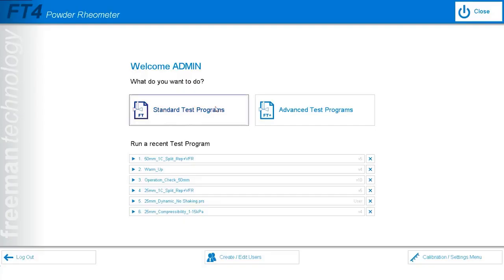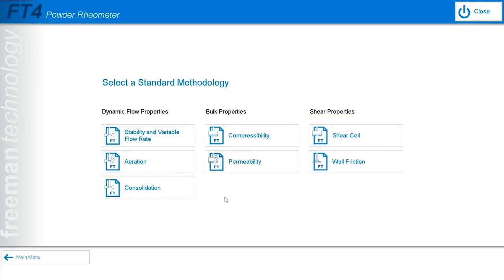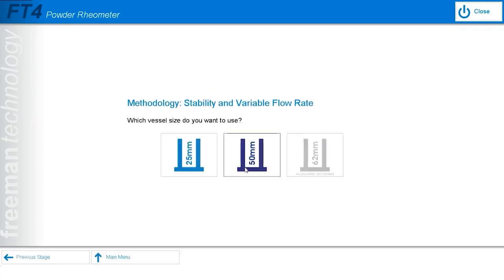On the software, I will select standard test programs, then select stability and variable flow rates. Next, we will select the vessel size. The FT4 has three different vessel size options to accommodate for different particle sizes and amounts of sample available. In this example, I'll be using the 50 millimeter diameter vessel, so I'll select that.